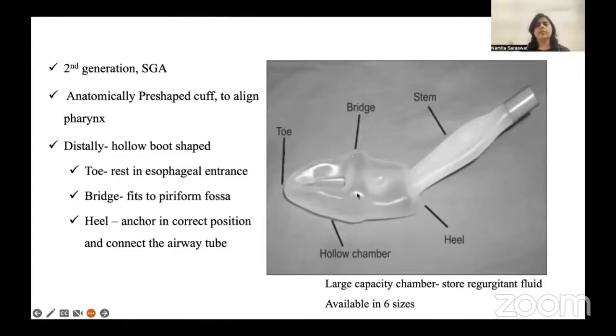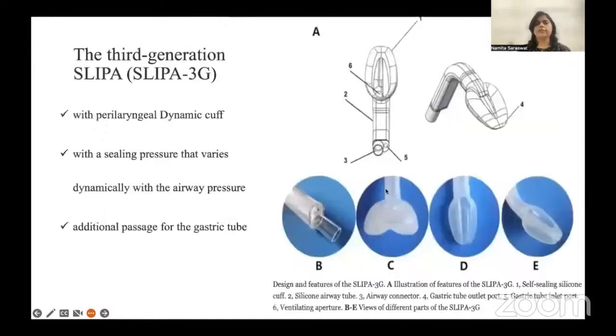These are the two bridges which will fit into the piriform fossa. This one is the heel. The heel will anchor in correct position and connect to the airway tube. This is the airway tube, also known as the stem. There is a hollow chamber for collecting the gastric secretion. Now in the market, third generation SLIPA has also been introduced. Why is it called third generation? Because it has a perilaryngeal dynamic cuff, that is, the sealing pressure will vary dynamically whenever the airway pressure varies. It also has an additional passage for a gastric tube.